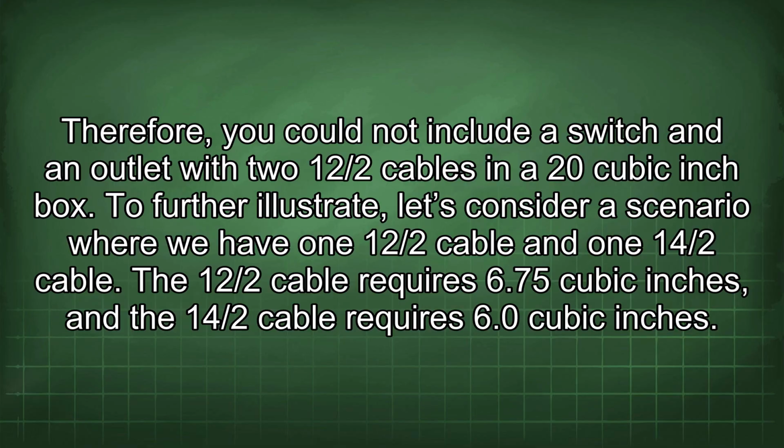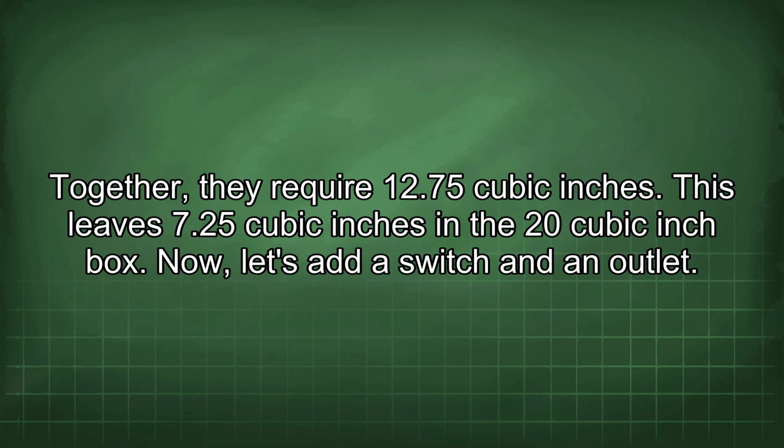To further illustrate, let's consider a scenario where we have one 12/2 cable and one 14/2 cable. The 12/2 cable requires 6.75 cubic inches, and the 14/2 cable requires 6.0 cubic inches. Together, they require 12.75 cubic inches. This leaves 7.25 cubic inches in the 20 cubic inch box.